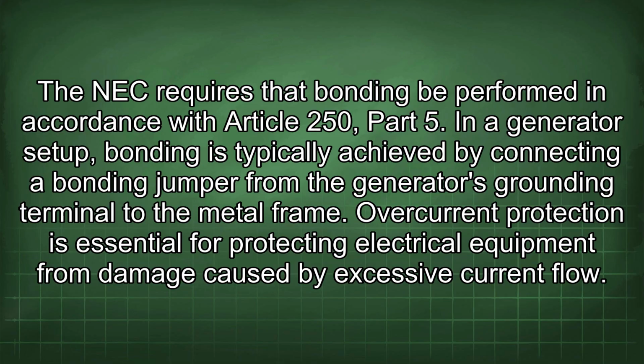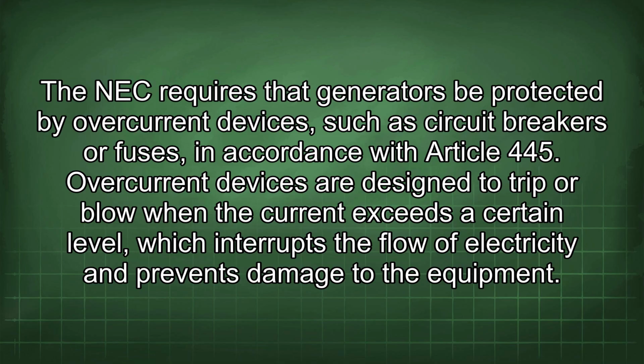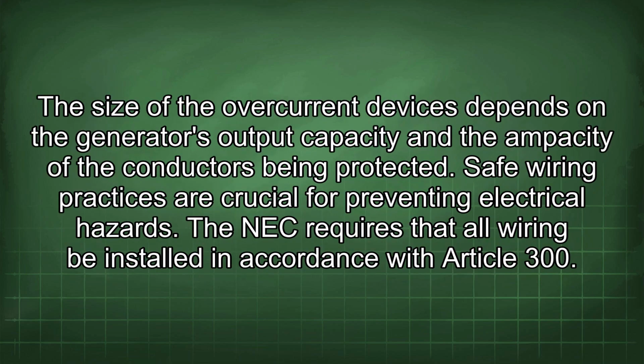Overcurrent protection is essential for protecting electrical equipment from damage caused by excessive current flow. The NEC requires that generators be protected by overcurrent devices such as circuit breakers or fuses, in accordance with Article 445. Overcurrent devices are designed to trip or blow when the current exceeds a certain level, which interrupts the flow of electricity and prevents damage to the equipment. The size of the overcurrent devices depends on the generator's output capacity and the ampacity of the conductors being protected.